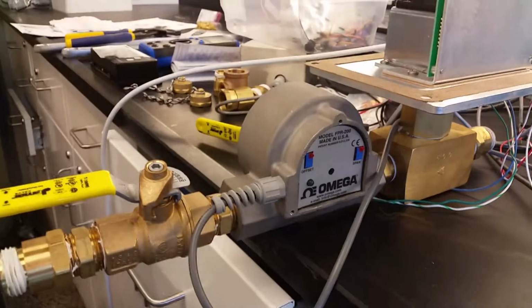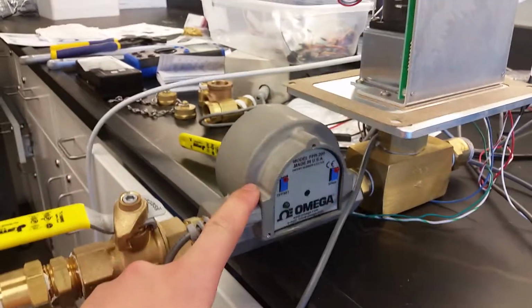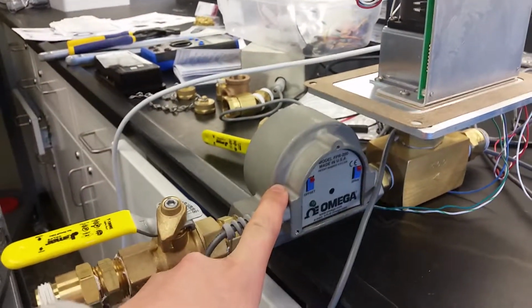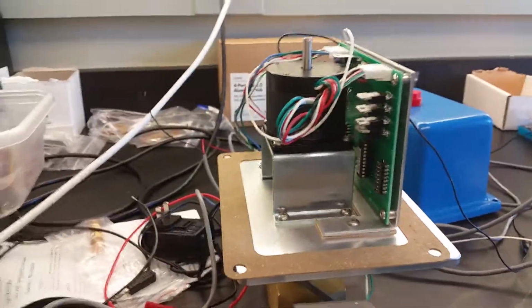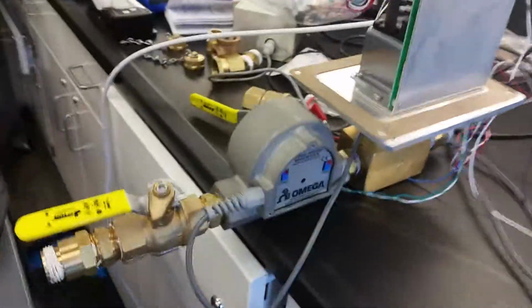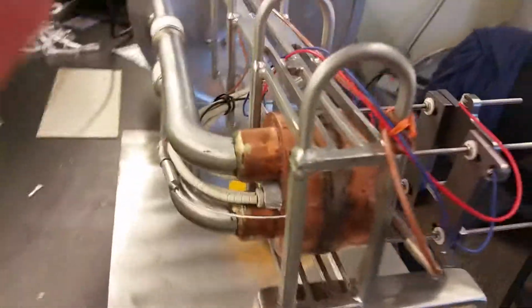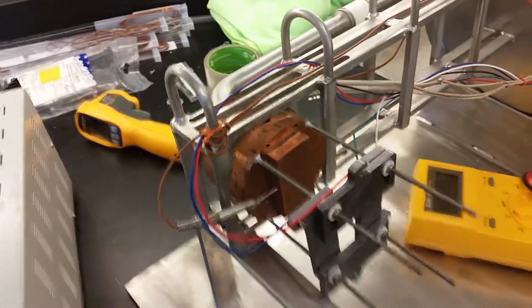I can do this from my Omega flow rate transducer, which tells me my output and sends a signal to my PID controller here, which goes to this proportioning solenoid valve that takes a 4 to 20 milliamp control signal. So I'll be able to adjust my process value from my set value, regulate the flow, and communicate with another thermocouple back here to get a cooling control system in place.